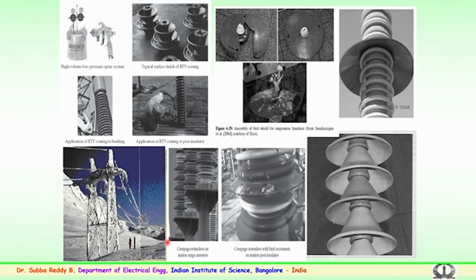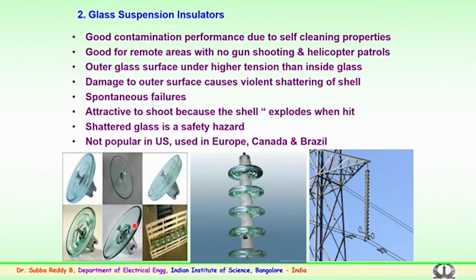a lot of revenue, particularly for the utilities to maintain and clean up these things, else the flashover will definitely happen because of the conduction of the surface, with ice formation which is continuously happening in cold countries. So, a lot of measures have to be taken by the utility or the transmission engineers, which is very important particularly during the monsoon, during the fog, during the icy conditions in the field.